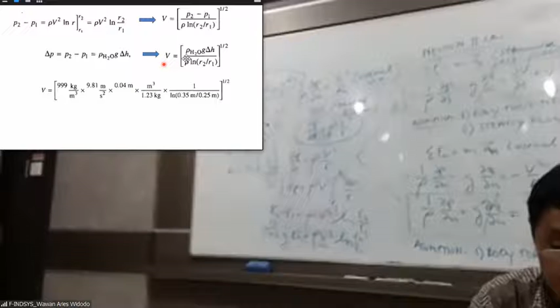This is the velocity based on the information in this problem. This is the outside radius, this is the inside radius. This is the density of air. And 0.04 is the height of the differential liquid. The velocity is actually 30.8 meters per second, multiplied by 0.1 meter multiplied by 0.3 meter. This is the area of the duct. This is the velocity inside the duct.